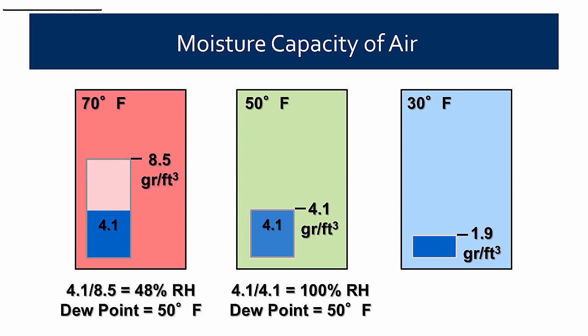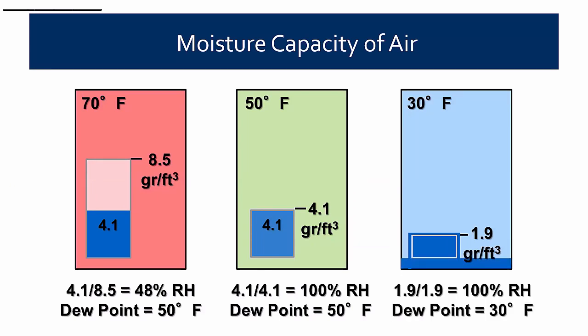If we cool that air down to 30 degrees Fahrenheit, it will only hold 1.9 grains per cubic foot, so that excess water has to leave — it can't be in the air anymore. The remaining 1.9 grains leaves the air at 100% relative humidity, but we've taken moisture out of the air, so the dew point changes. The only way dew point can ever change is if you add moisture or take moisture out. Dew point is not changed by temperature like relative humidity — which is why we want to look at dew point rather than relative humidity when examining condensation moisture problems.